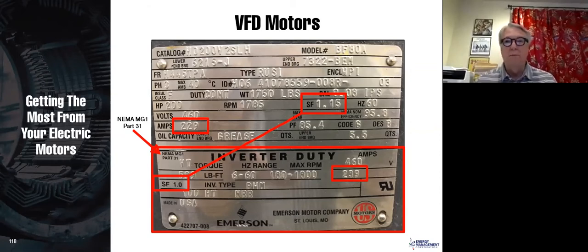Again, most nameplates on motors do not have this inverter duty section on the nameplate. And so if it doesn't have this section on the nameplate, you're going to say that the full load amps is the same, whether it is running on a VFD or not.